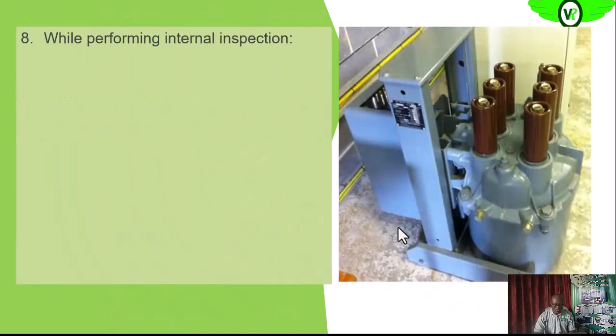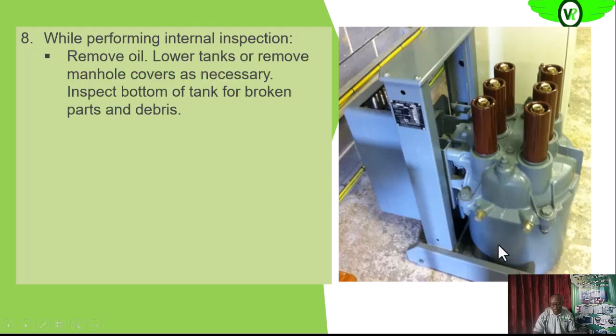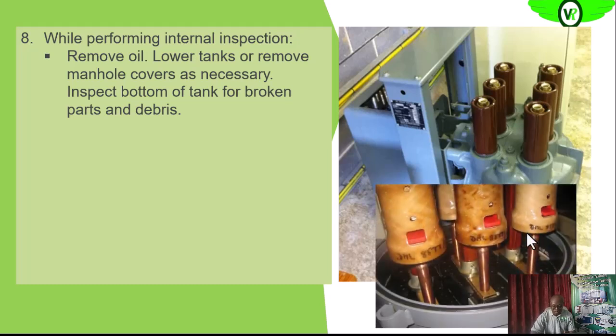So the next thing we need to do is perform some internal inspection if our routine inspection involves opening the circuit breaker. We also want to look at the tank after removing the oil, checking for any visible signs of broken parts. If there are broken parts, we want to ascertain where that part is broken from. We also want to check if there is physical debris in the bottom part of the oil or in the oil itself.